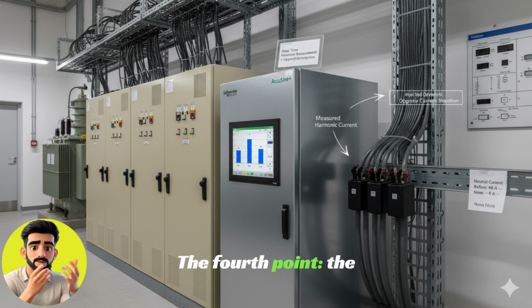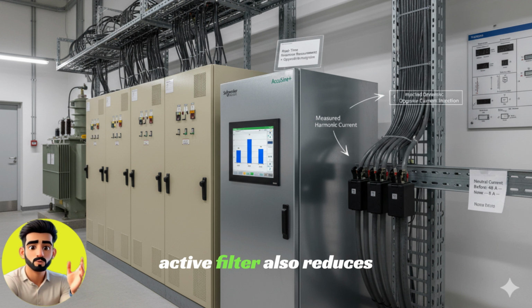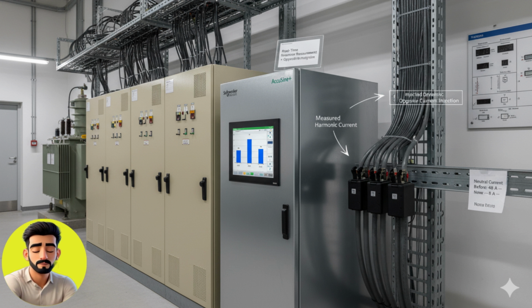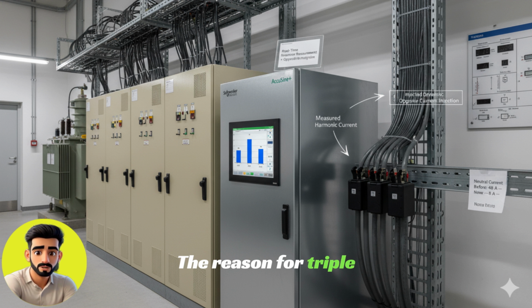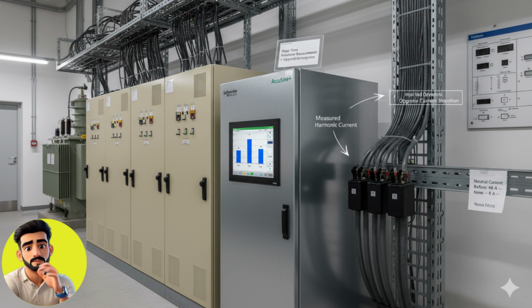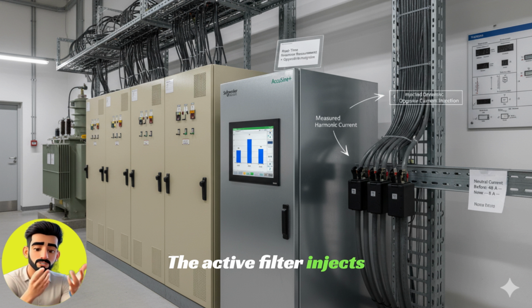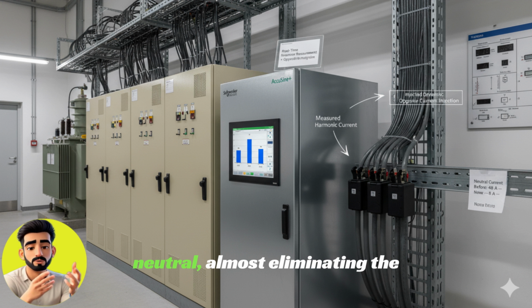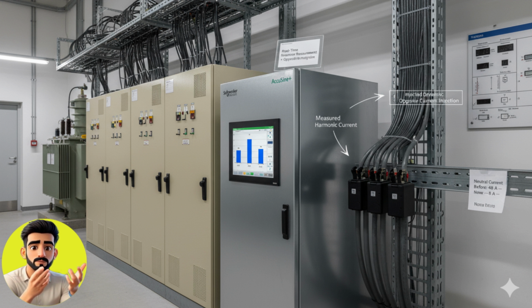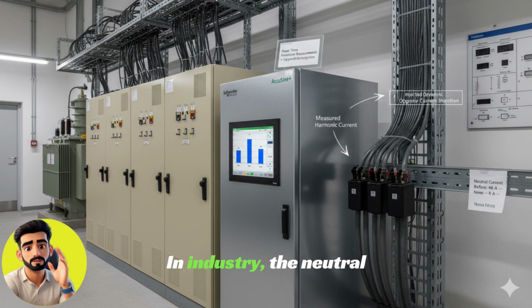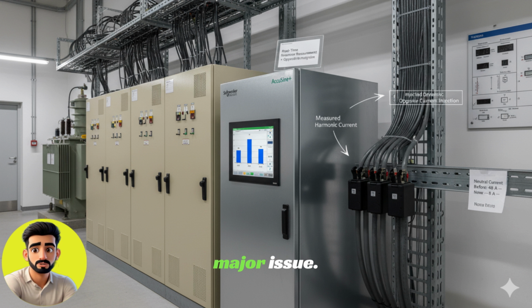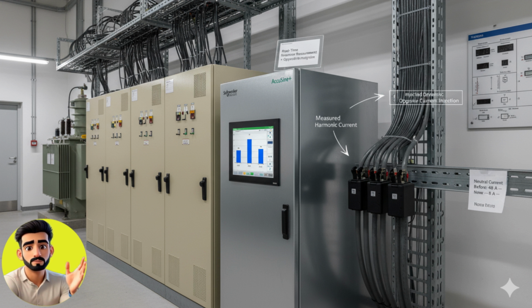The fourth point, the active filter also reduces neutral current. The reason for triplen harmonics is unwanted current flow in the neutral conductor. The active filter injects opposite current into the neutral, almost eliminating the overload of the neutral conductor. In industry, the neutral conductor burning is a major issue. Triplen harmonics are the reason, and active filters solve the issue completely.